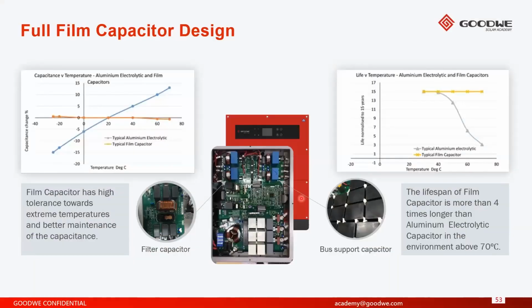So in our inverters, we've moved away from using a traditional electrolytic capacitor to a thin film capacitor, which runs at a much lower temperature and lasts 4 times longer than the standard electrolytic capacitor. And it has a much higher tolerance to higher ambient temperatures. So typically the capacitor itself and the inverter will have a longer lifetime.